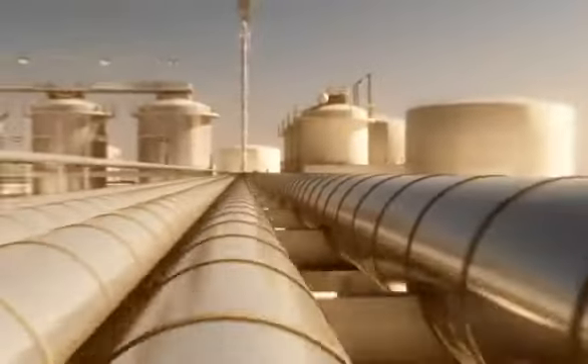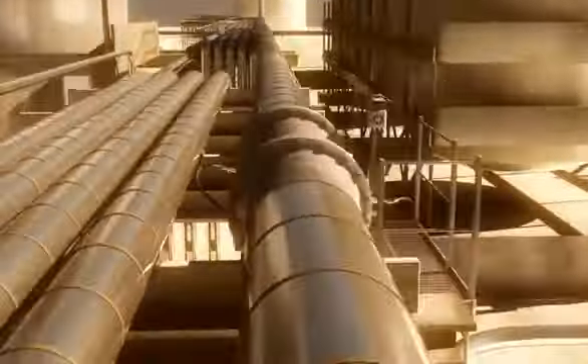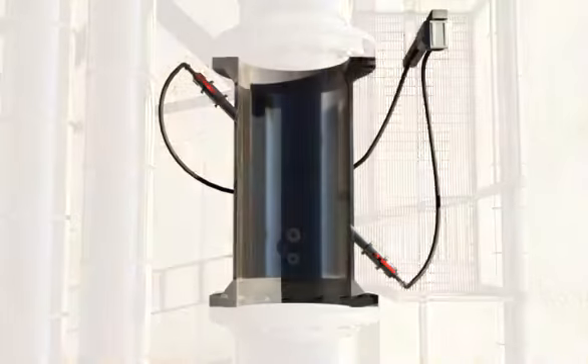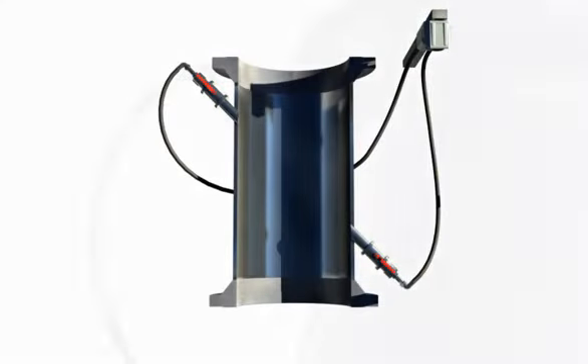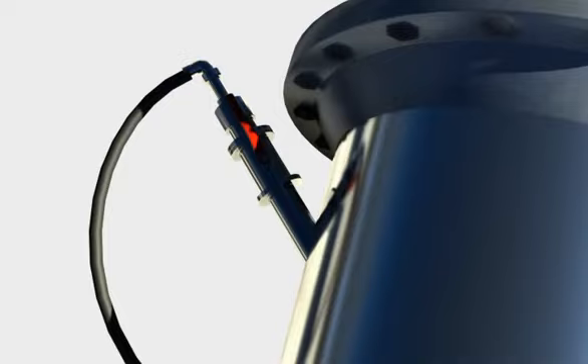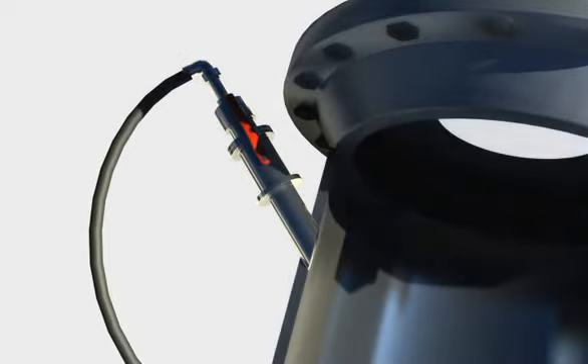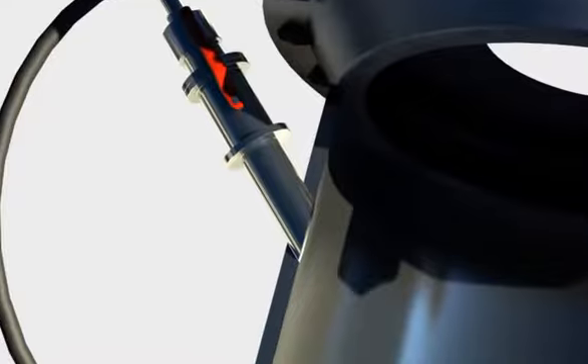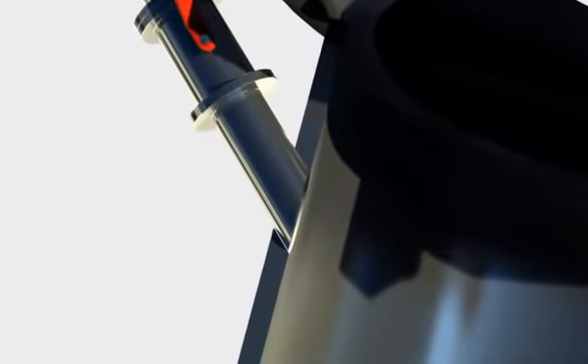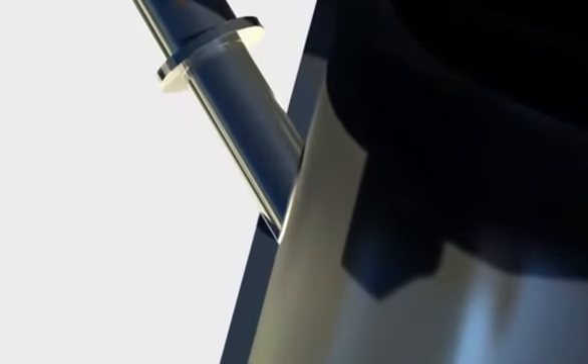The extreme high velocity of the flare gas can also cause damage to all intrusive parts of the instrument. To this end, Fluenta has a policy of not having any part of the sensors within the full flow profile of the flare line. The ultrasonic sensors on a Fluenta flare gas meter are always installed flush to the inner pipe wall, which gives the full flow profile measurement with the largest time resolution. This increases the accuracy at low velocity and also protects the sensors from high velocity.